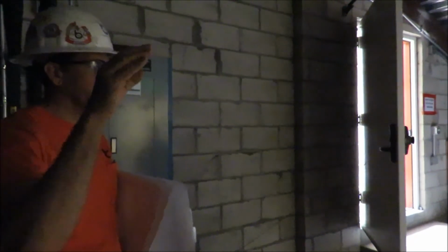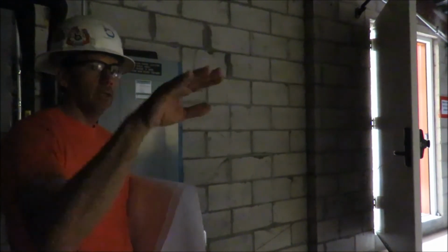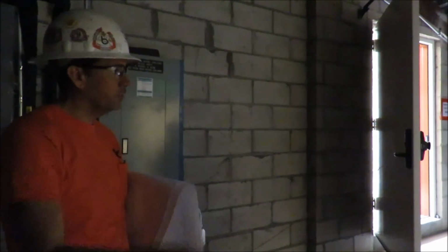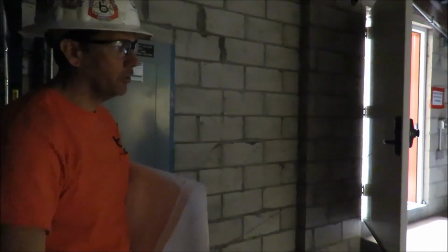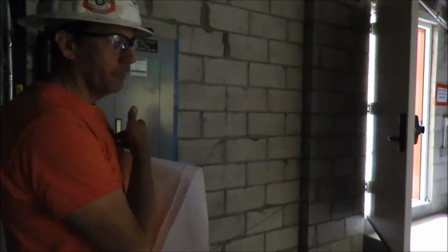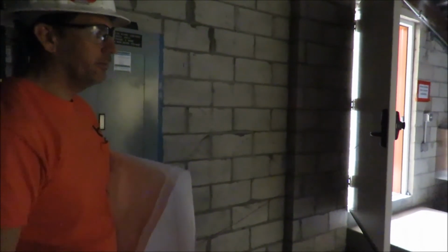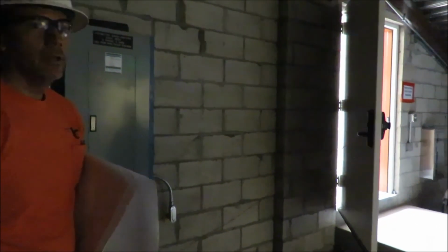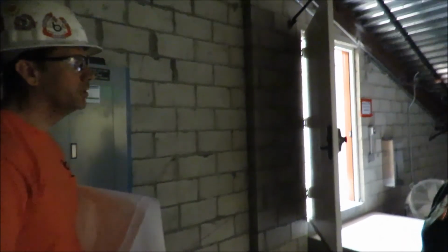If you have a fire alarm and power doesn't go out, this will take the people to the right floor where the fire alarm is not going off, open the doors, and trip the shunt breaker so that nobody can use the elevator after that. And after everything's said and done, this is where you go to reset it.